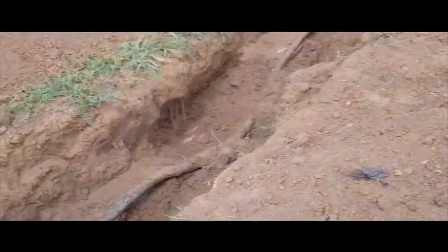You know, how did we get here? Firstly, the whole infrastructure, be it electricity, water, sewer, stormwater of Empoleni is very old. Three Rivers in particular, cables installed in 1956, and we took pictures because we had to go and be there to see what's happening. They were still labeled during those years as to when it was manufactured, when it was installed. 1956. Nothing's been done to it in terms of maintenance. Obviously, the cable doesn't need that much maintenance because it's not oil cable, so it doesn't need refilling. But because there's not been enough operational expenditure on repairs and maintenance, capital expenditure on replacement and refurbishment done on the infrastructure, a lot of those cables are damaged.